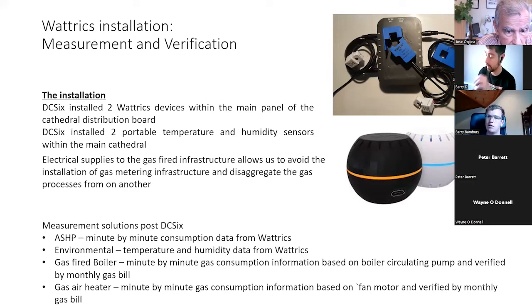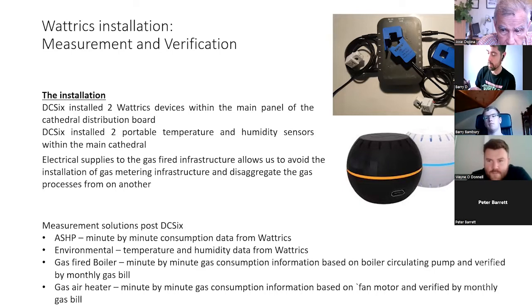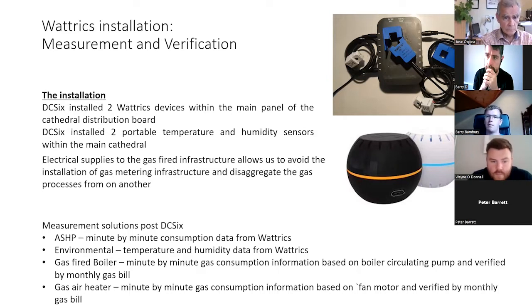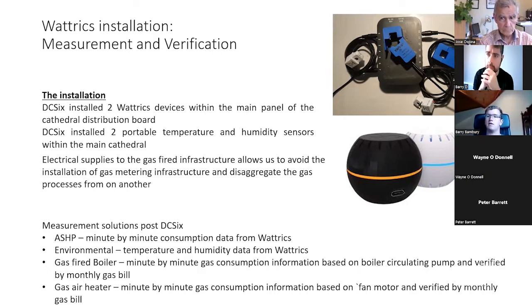So that gave us an idea of the operating hours every day, or time series operating hours, of that piece of plant. We were also able to put a CT clamp on the circulating pump for the boiler that heats the back offices. And we were able to look at the nameplate on both that roof-mounted gas heater and the traditional one that heats the back office. From the two of them, we were able to estimate, looking at how often they're operating, how many kilowatt hours you expect these two pieces of plant to use every month.